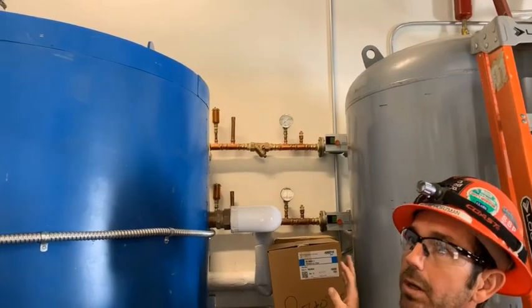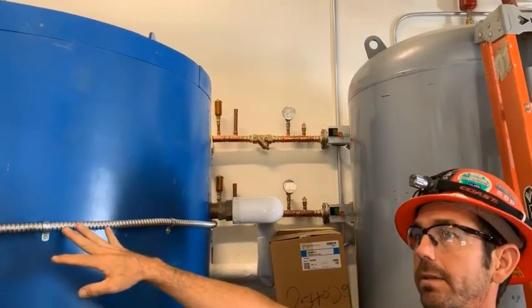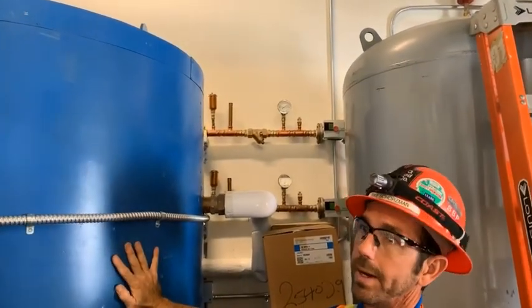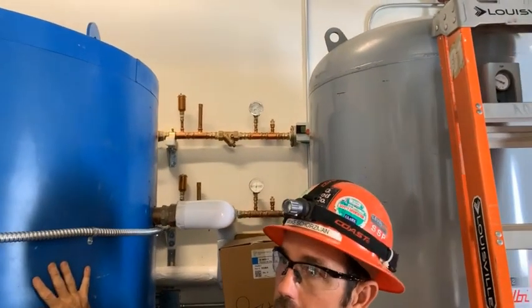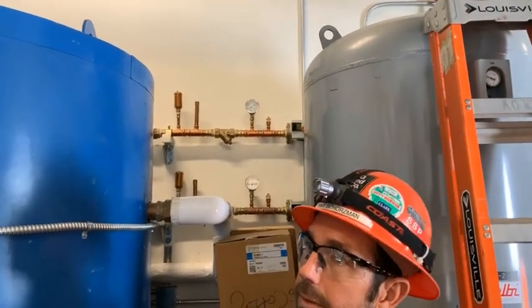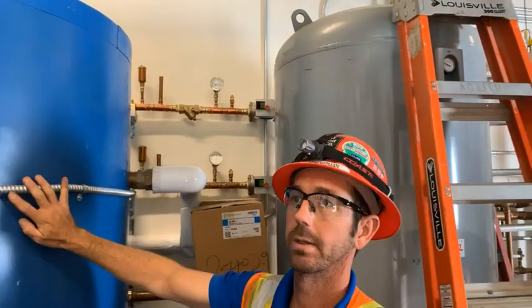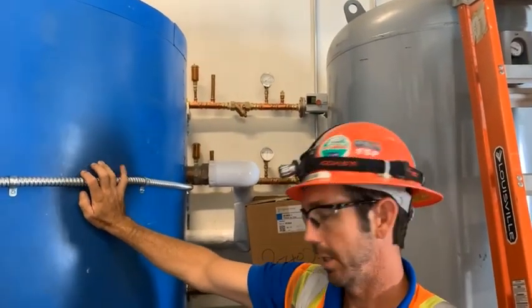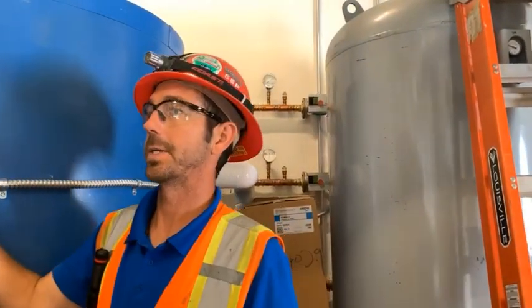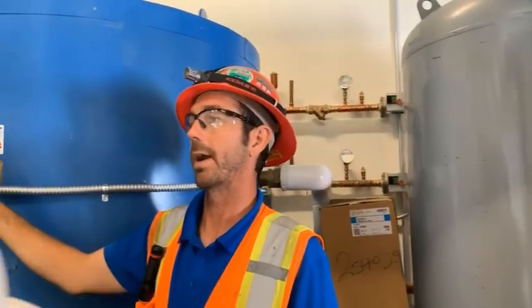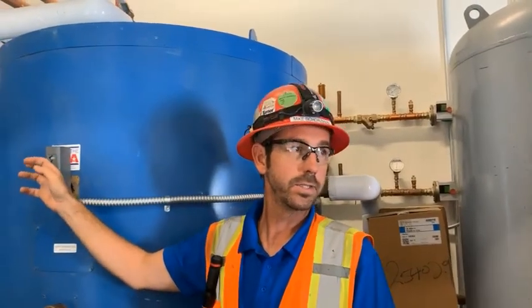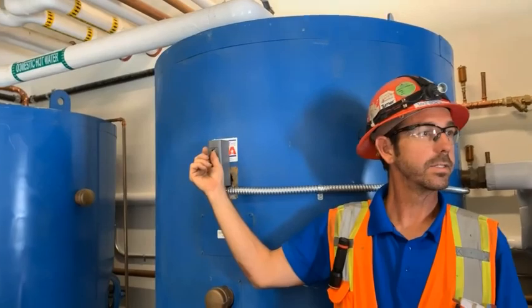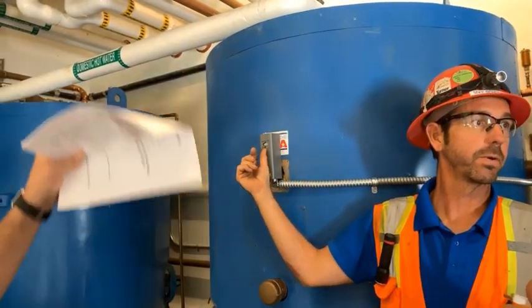Potentially off of an aquastat. So if the tank is satisfied, the pump might not be running. The one pump could be calling versus the other. It just depends on the dynamic of the water flow, if it needs more water flow or not. It could be only one temperature. So we're trying to maintain 140 right here at this aquastat, okay? This setting on the aquastat is what's turning the pump on and off, and it needs to be 140.